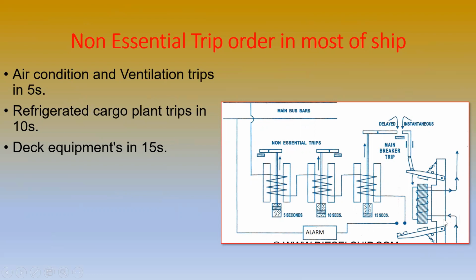Here the load current passes through this electromagnetic coil, and by the action of the spring with the relay movement, the trip is activated. When the current goes beyond a particular limit, the spring will move, and it is attracted towards the trip circuit. So every 5 seconds: air conditioning will get tripped, then at 10 seconds refrigeration, and at 15 seconds the deck equipment. The dashpot is provided as a time delay.